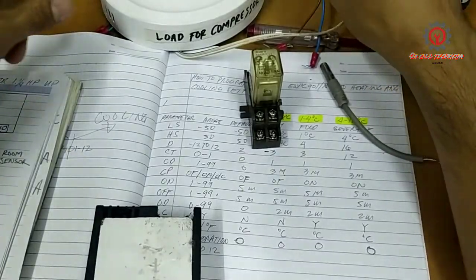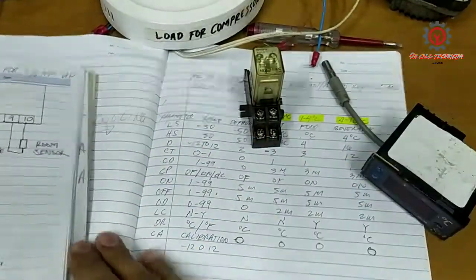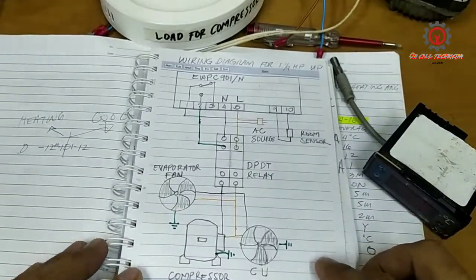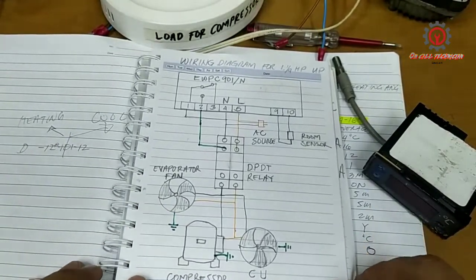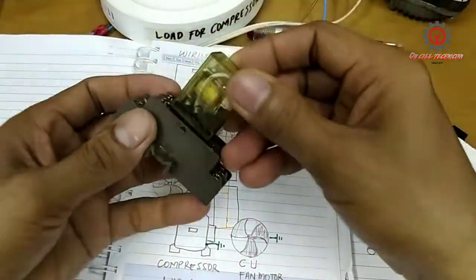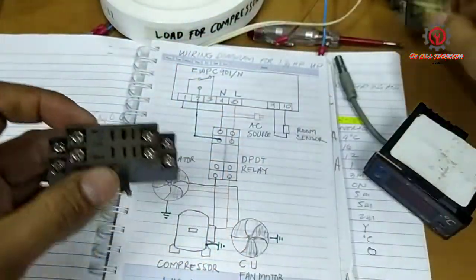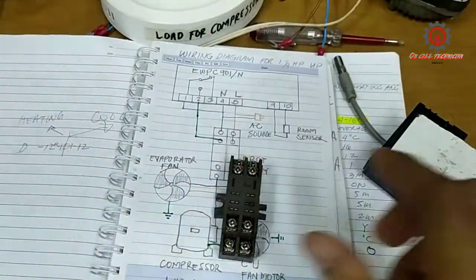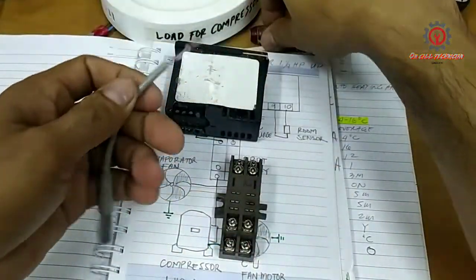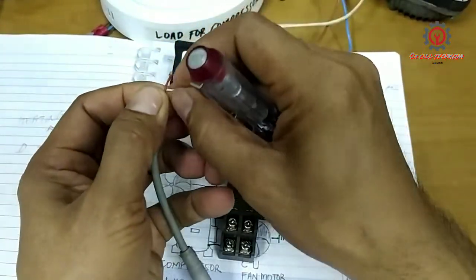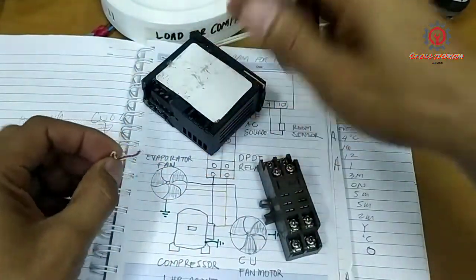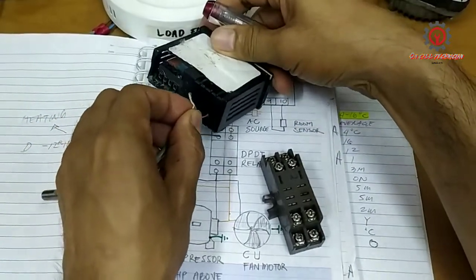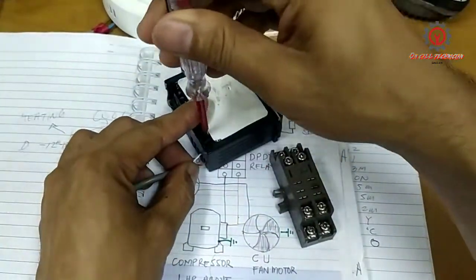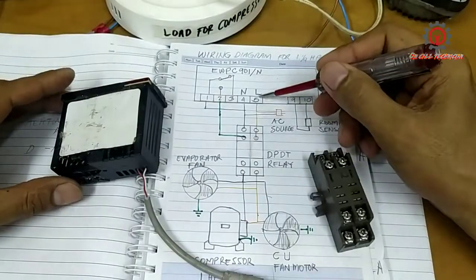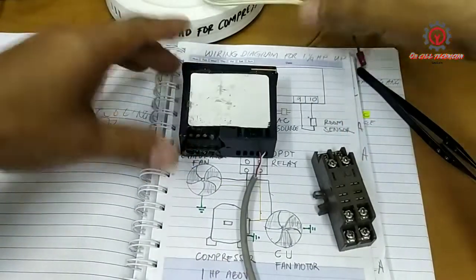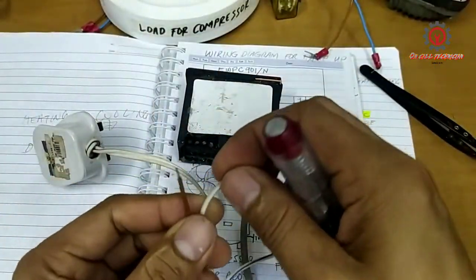Let's begin, guys, with the wiring diagram, and I have made the wiring diagram here. Just screenshot if you want to copy it, and let's start wiring it. First, we can install the probe sensor to terminal number 9 and terminal number 10. Next is terminal number 5, my AC source, and this is my live.